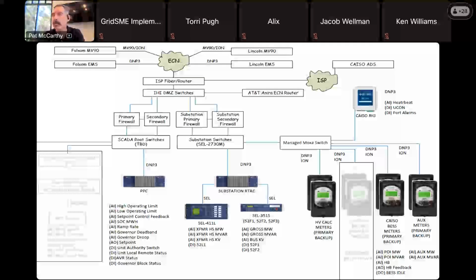As you're moving through, maybe your substation points and your meter hit the time to change directions, try something else, and start loading up different revenue data from a different device. You'll transition back and forth: set up a revenue meter, take a quick read, let it work while you test the next device in the telemetry points list.